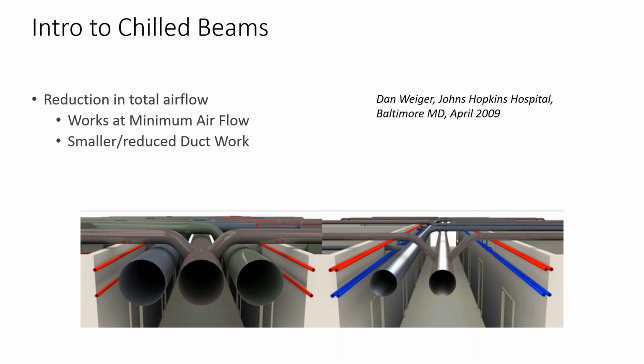And so you have obviously a supply, return, and exhaust, and then the hot water piping for heating the spaces at the VAV. And then on the right side, you can see the chilled beam system that they analyzed, where we not only reduced the diameter of those mains quite significantly, down to a 7-inch diameter connection, at least on the branch offs to the chilled beams.